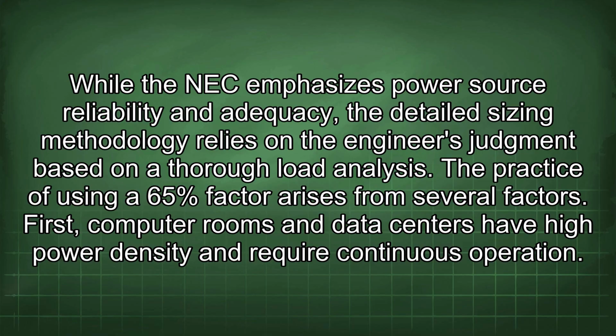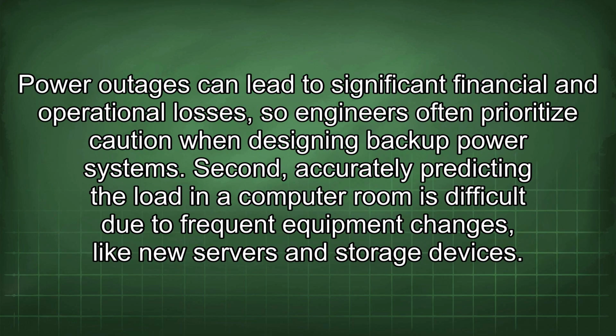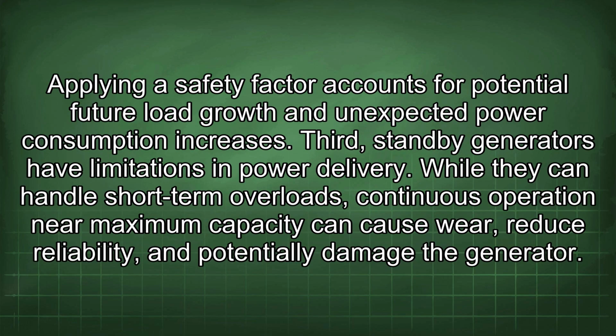The practice of using a 65% factor arises from several factors. First, computer rooms and data centers have high power density and require continuous operation. Power outages can lead to significant financial and operational losses, so engineers often prioritize caution when designing backup power systems. Second, accurately predicting the load in a computer room is difficult due to frequent equipment changes, like new servers and storage devices. Applying a safety factor accounts for potential future load growth and unexpected power consumption increases.